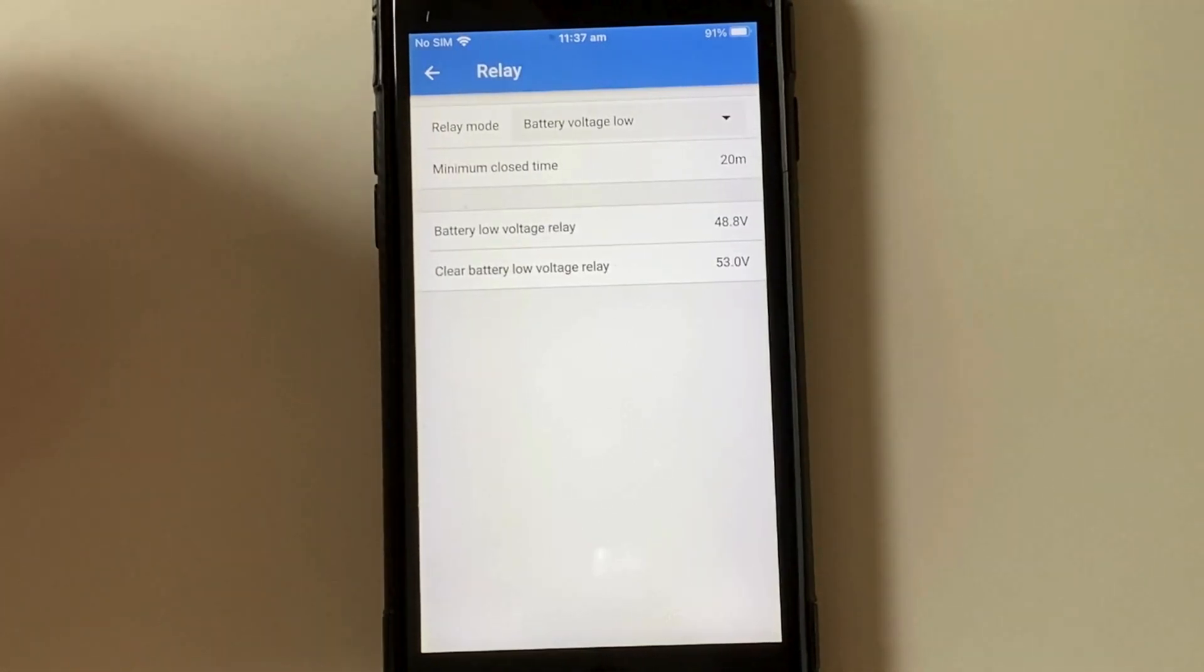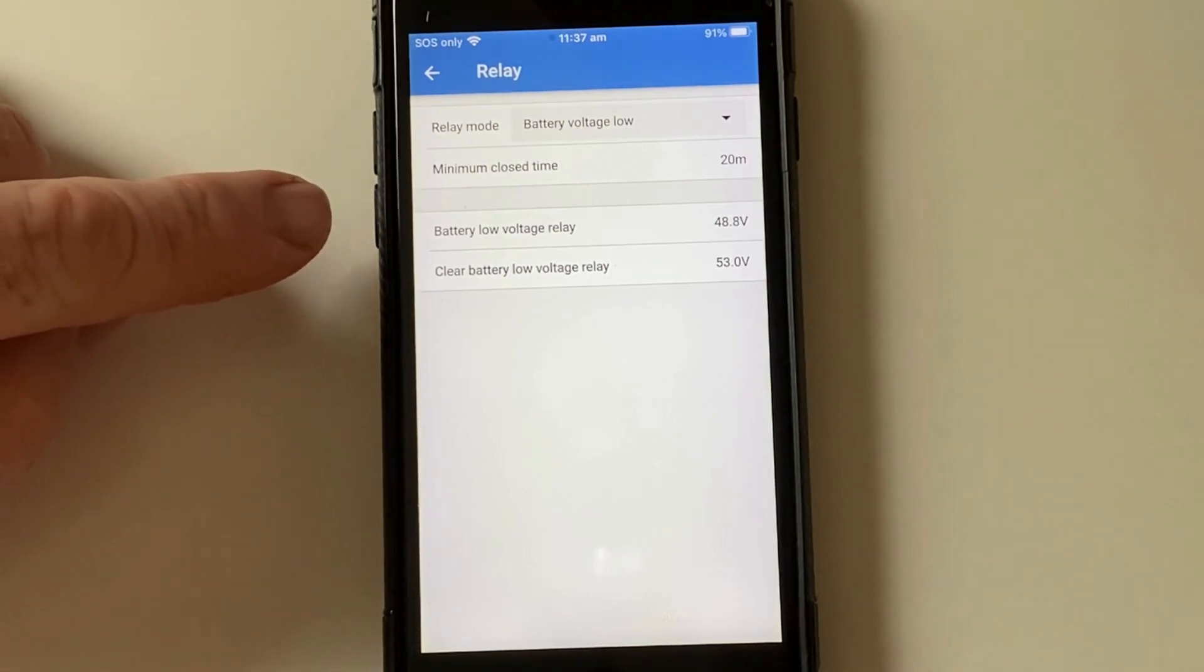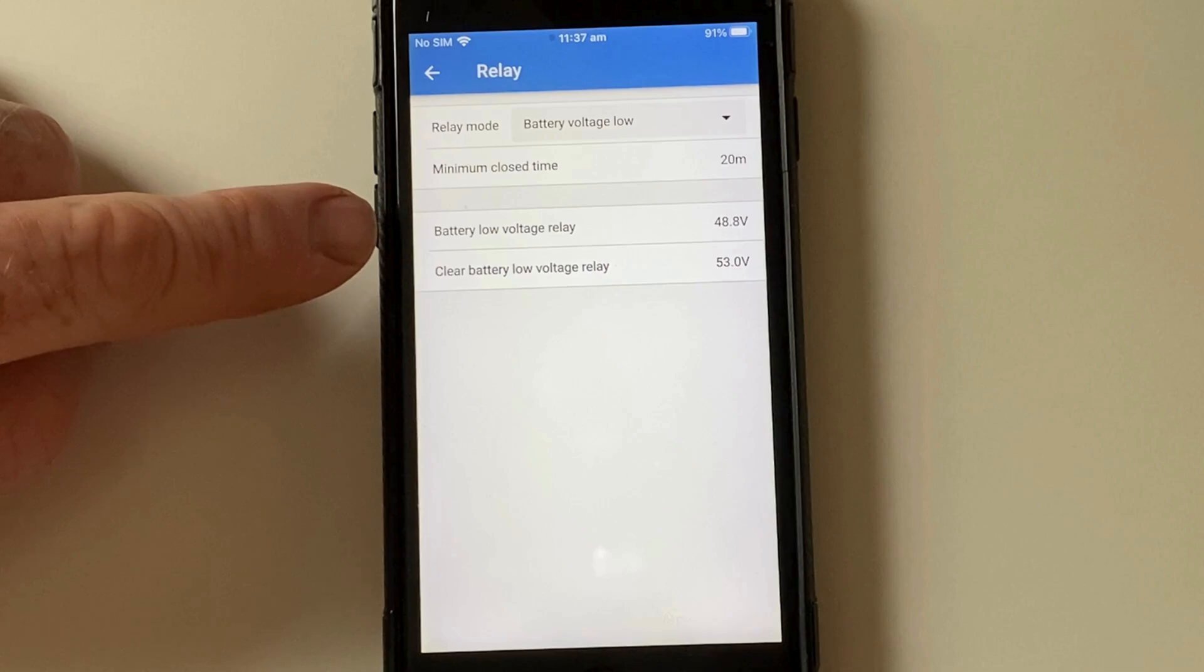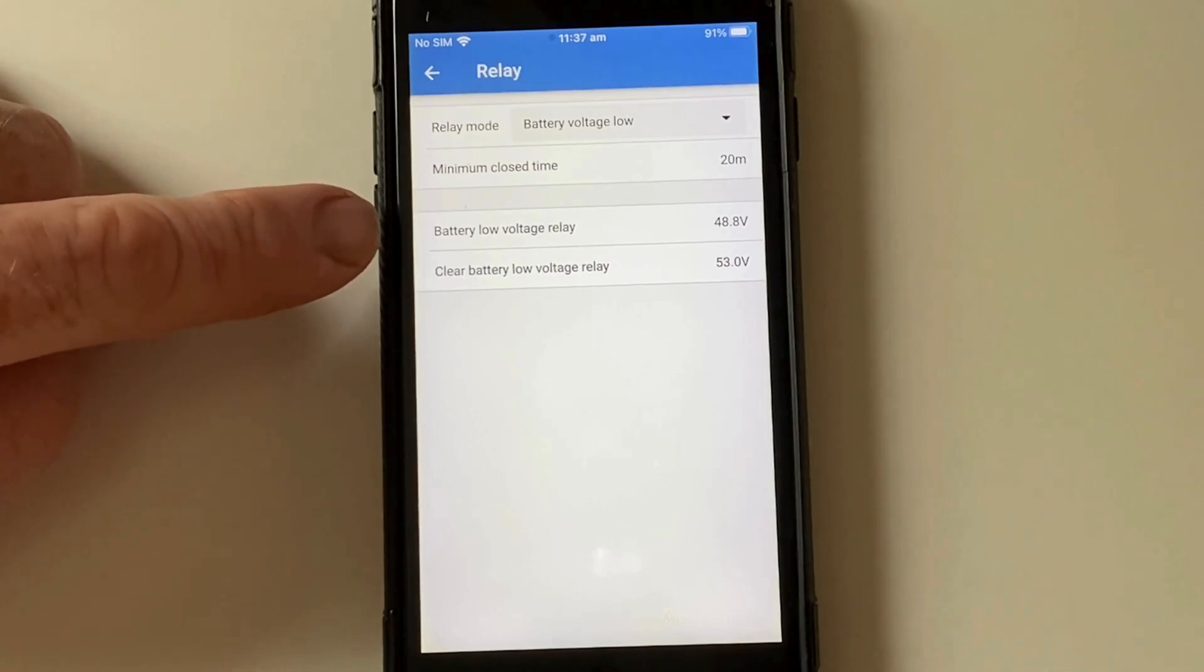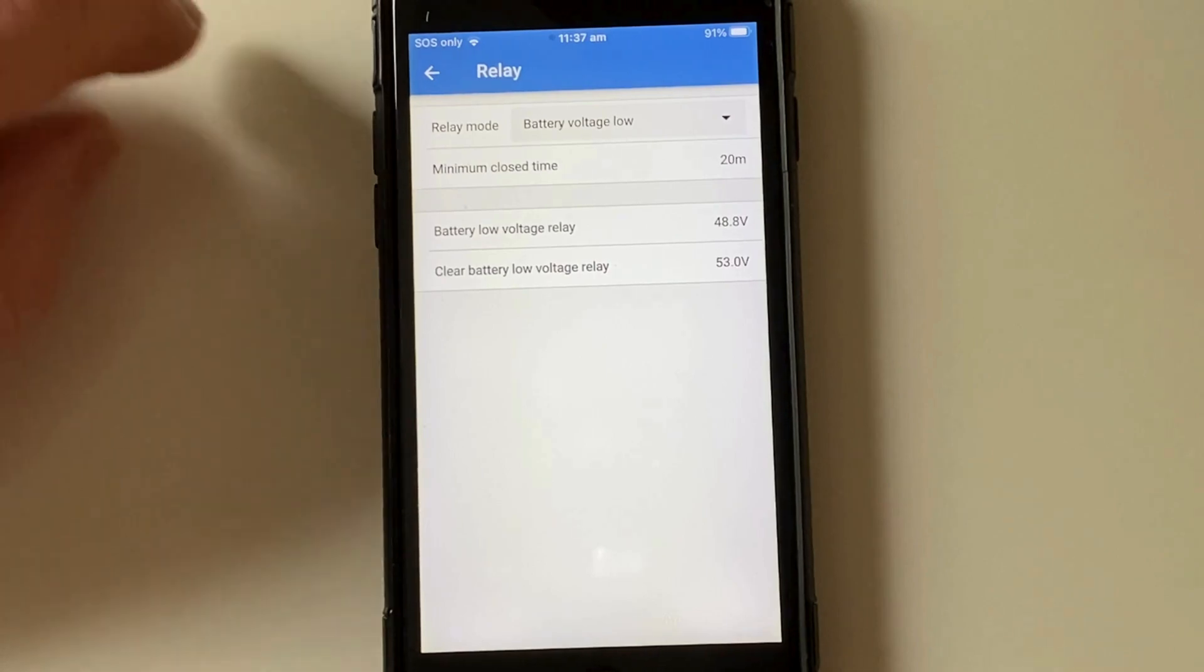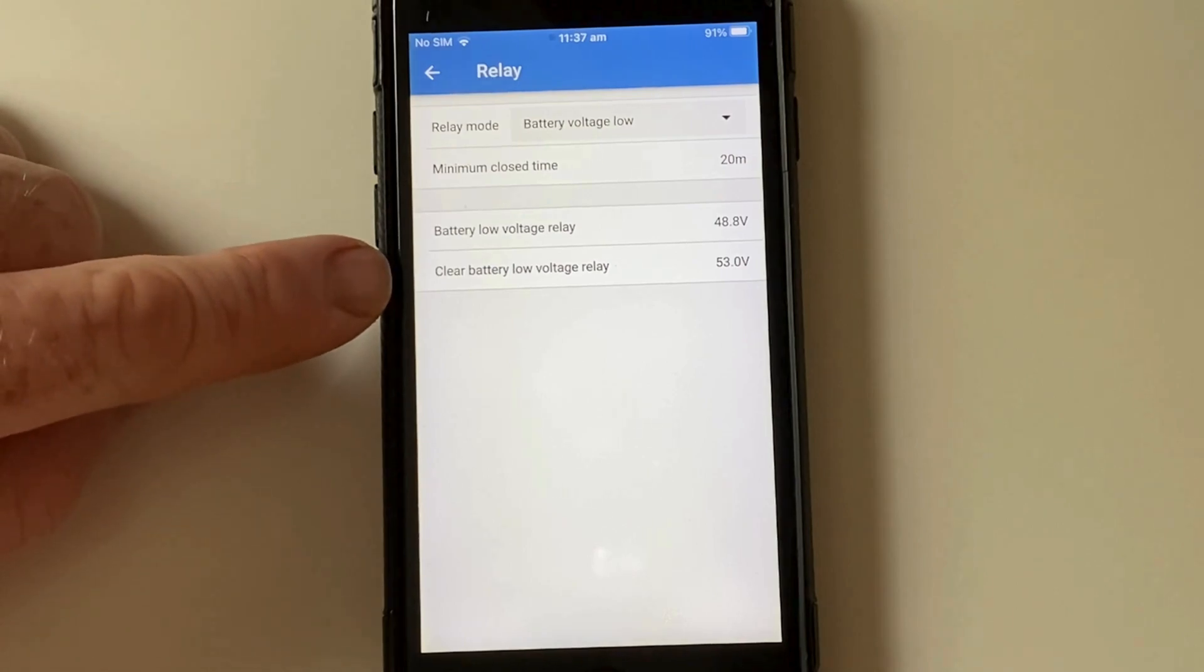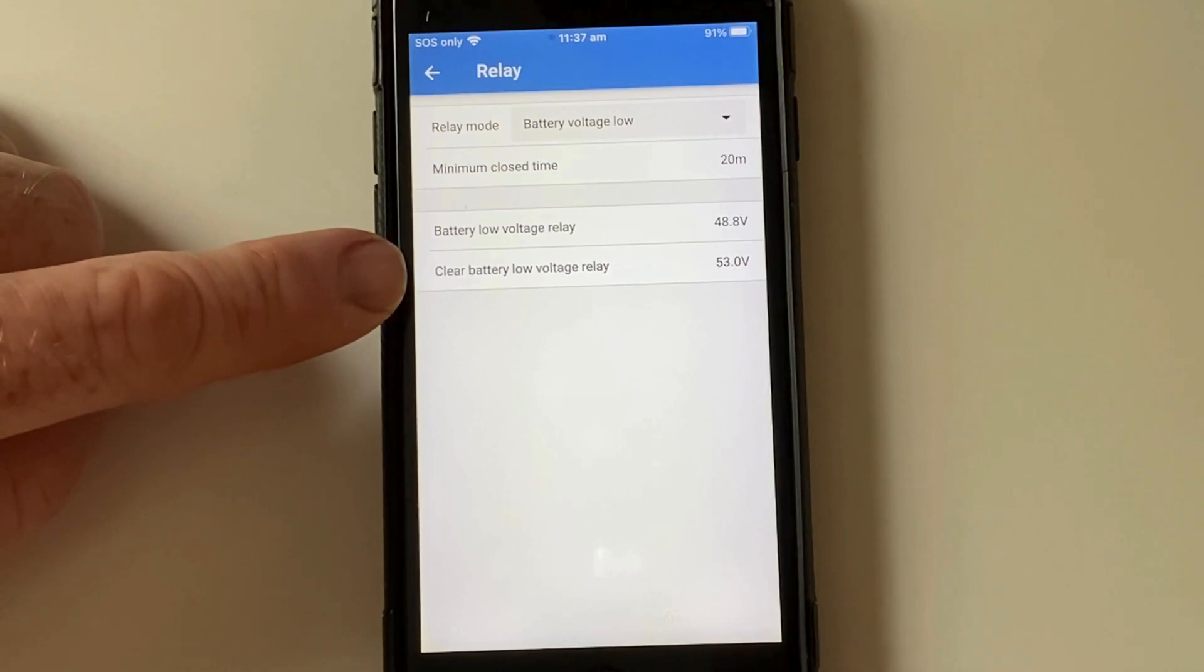So this is the relay that triggers the generator. So at 48 volts, 48.8, the relay will be triggered. So once the battery is drained down to that much, the generator will come on, start charging the batteries. I've got a minimum close time on that relay for 20 minutes. And then the relay will clear and remain open at 53 volts until it receives another low battery signal.